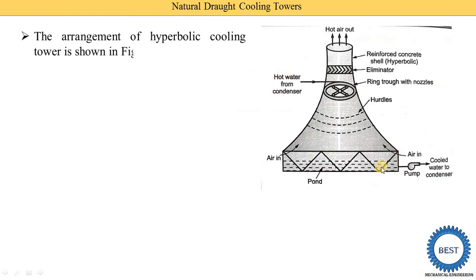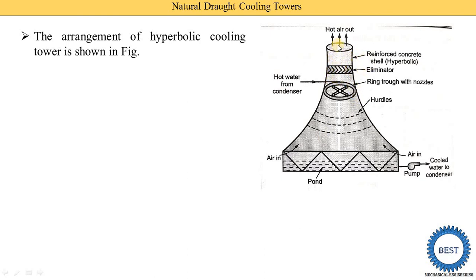Here is the diagram of a natural draft or hyperbolic cooling tower. It has various components: the hyperbolic profile, and at the point of minimum area in the hyperbolic profile, a ring of nozzles is installed. A number of nozzles are arranged on this ring and hot water from the condenser is sprayed through them. Wooden hurdles are placed inside, water is collected at the bottom, and air enters from the bottom. An eliminator is installed to absorb water particles from the air, and hot air exits from the top.